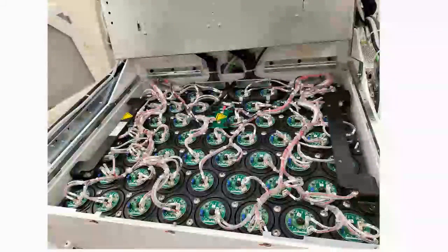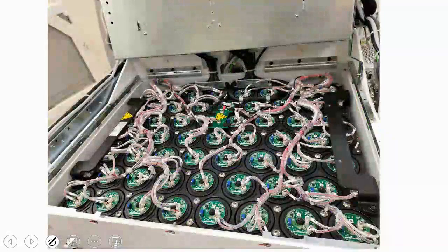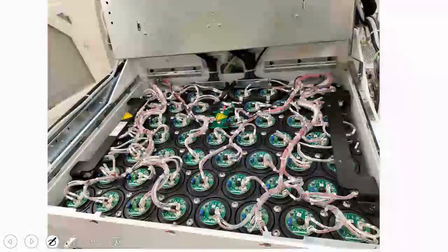This is what it looks like when we open the back of the head. So here is our head. Do you see this head? The open collimator is placed here in this area. This is head 1, and this is head 2. This camera consists of a pair of heads. This view from above shows the shape of the photomultiplier tubes, which can sometimes reach up to 90 photomultiplier tubes.